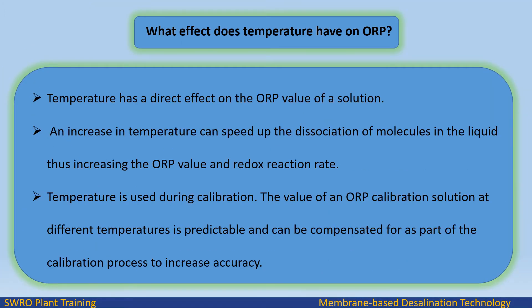An increase in temperature can speed up the dissociation of molecules in the liquid, thus increasing the ORP value and redox reaction rate. Temperature is used during calibration. The value of an ORP calibration solution at different temperatures is predictable and can be compensated for as part of the calibration process to increase accuracy.